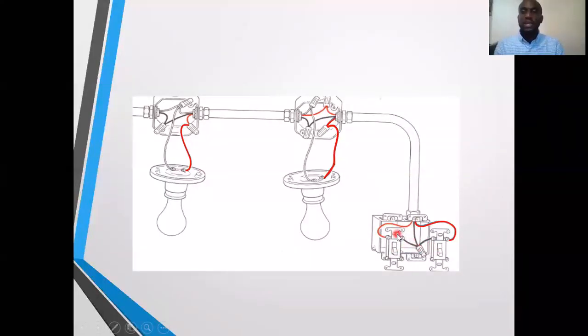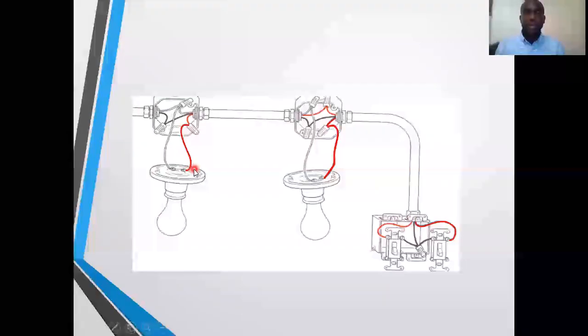When you share it between both switches, then you have two independent lines, switch feeds, that are going through the main pipe. When they go back through the main pipe, you will connect one to the first lamp, then you will send the next one through and connect to the next lamp. And again, we are only connecting switch feeds onto the brass terminal.